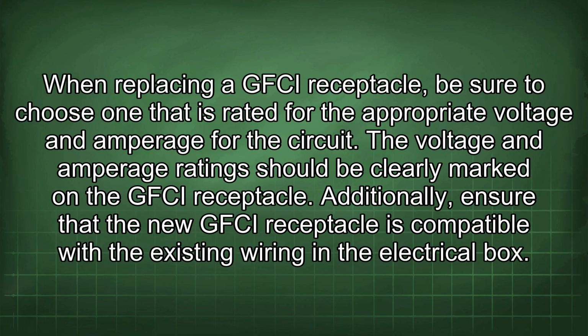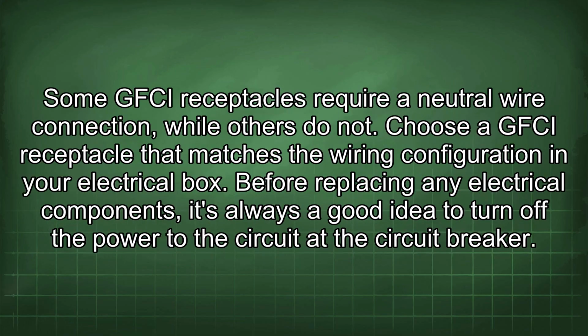When replacing a GFCI receptacle, be sure to choose one that is rated for the appropriate voltage and amperage for the circuit. The voltage and amperage ratings should be clearly marked on the GFCI receptacle. Additionally, ensure that the new GFCI receptacle is compatible with the existing wiring in the electrical box. Some GFCI receptacles require a neutral wire connection, while others do not. Choose a GFCI receptacle that matches the wiring configuration in your electrical box.